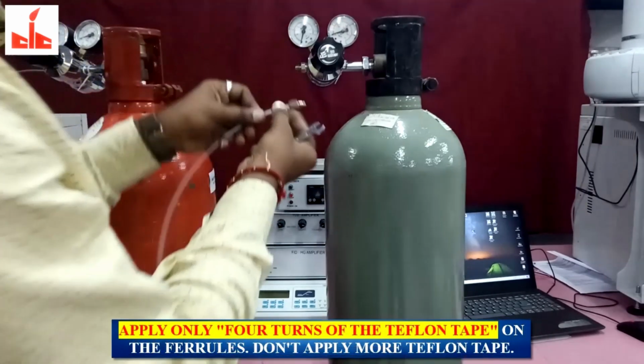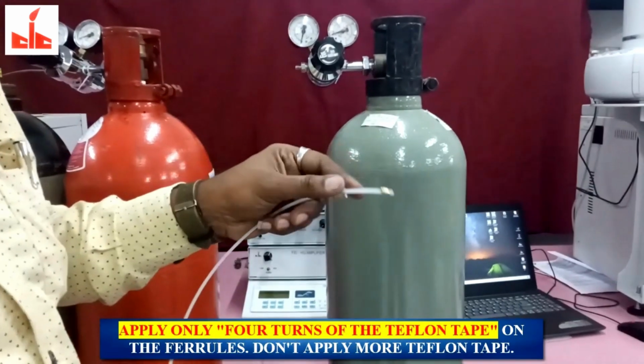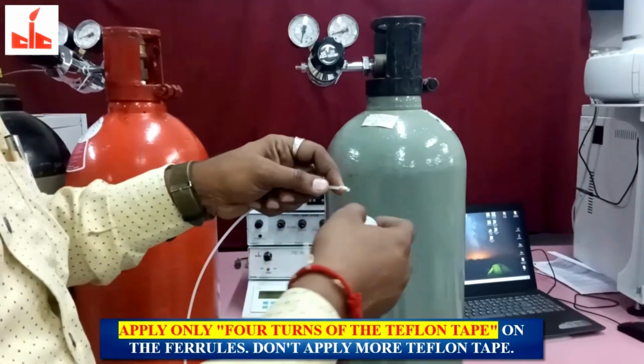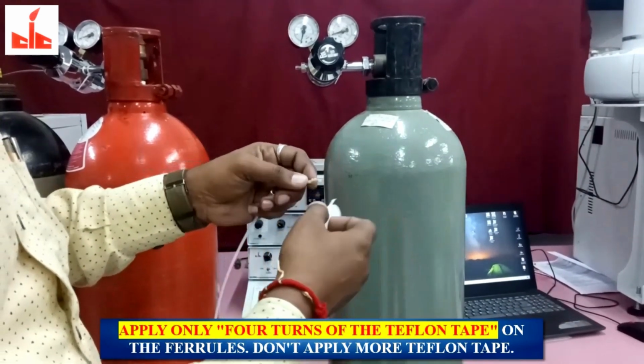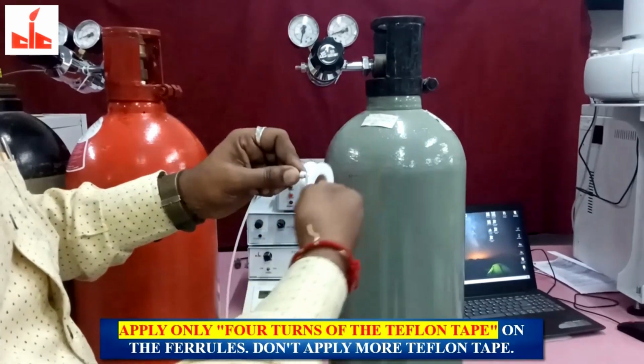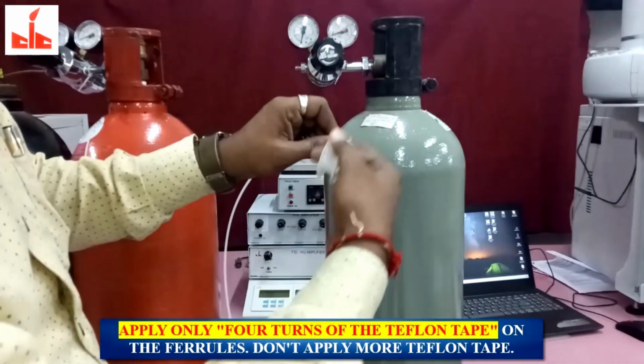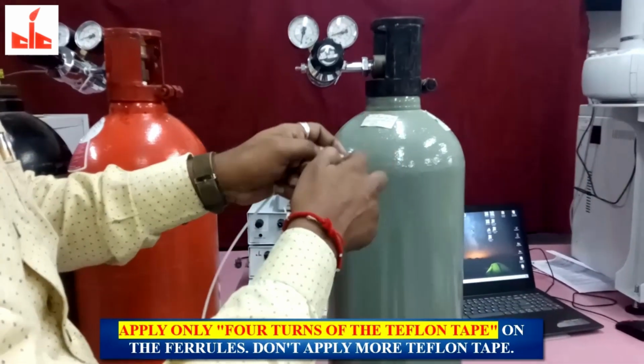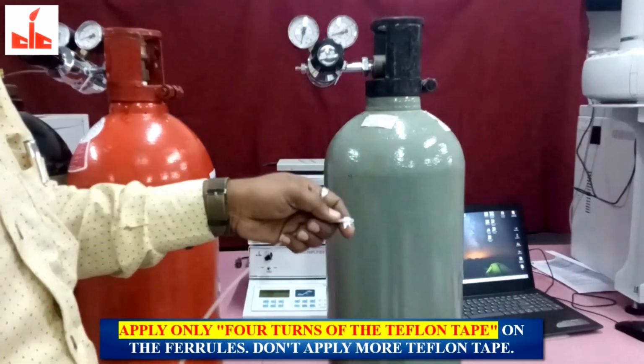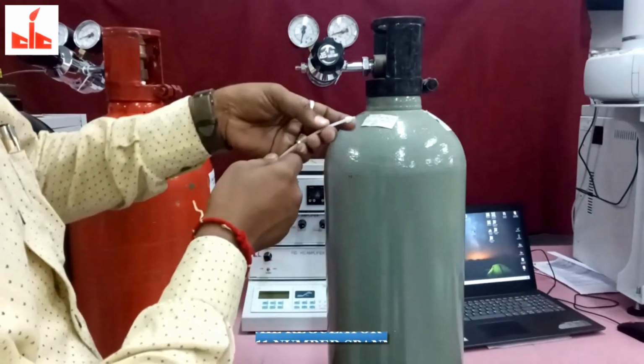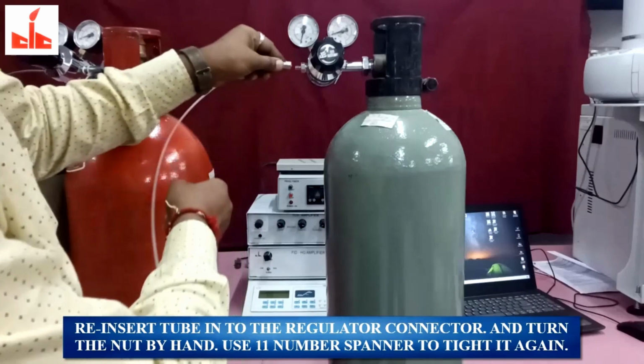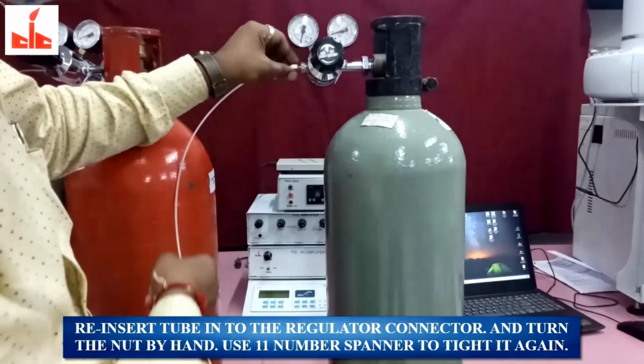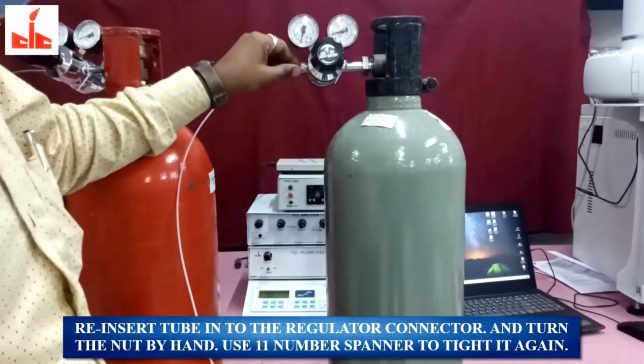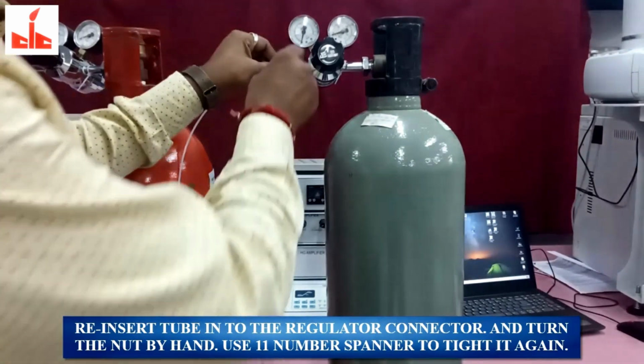Apply only 4 turns of the Teflon tape on ferrules. Don't apply more Teflon tape. Reinsert tube into the regulator connector, and turn the nut by hand. Use 11 number spanner to tighten it again.